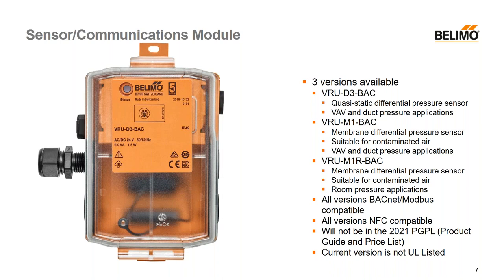It's a quasi-static differential pressure sensor, which means that even though it is a flow-through pressure sensor, the flow is so low it's almost considered a static differential pressure sensor. You can use this in both variable air volume and constant air volume applications, as well as duct pressure applications. We also have the VRU-M1-BAC. The M stands for membrane differential pressure sensor — it's the first iteration. One advantage of this sensor over the D3 is that it's suitable for contaminated air applications, and you would use it in the same applications: VAV, CAV, and duct pressure.